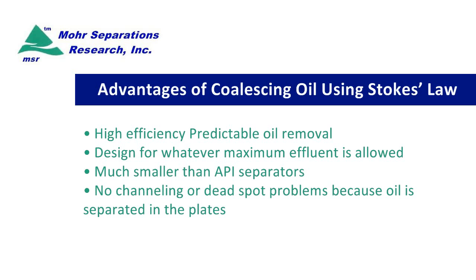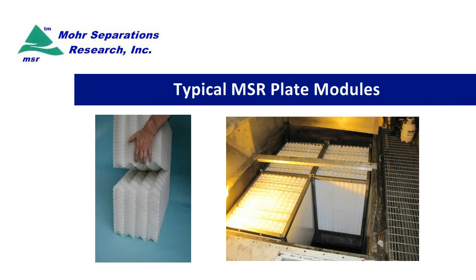There's no channeling or dead spot problems because the oil is separated within the plate media. If you have a large empty tank you'll get a lot of channeling and dead spots that are not doing any good for the separation. Here are some typical plate modules — you can see the underside of the plates where the coalescing actually occurs and the holes in the peaks of the plates where the oil weeps from peak to peak and comes out after it has been coalesced into large droplets.